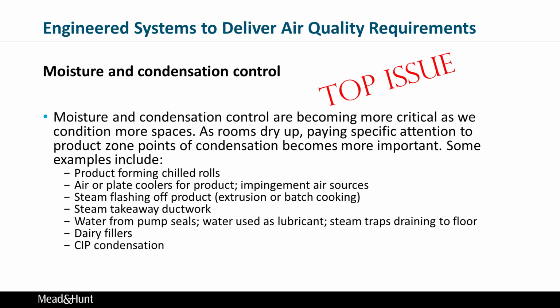Do you have wet floors? Do you have pieces of process equipment that are chilled or cooled in some way that have wet surfaces where you've got condensation issues? Do you have heat exchangers in the room that either leak steam or hot water or sweat because they aren't insulated? So you've got to go through all of these different things. There's other things like pump seals, dairy fillers, and other pieces of equipment that'll produce moisture in the room as well. So you've got to identify all of those and then use that information to design the system to try to get rid of all of it.